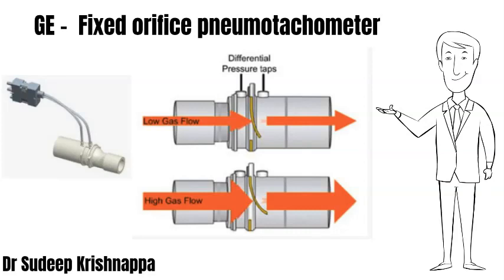In order to overcome this, the restrictor used is constructed in the form of a flap made of a synthetic material called Mylar. At low flow states, the flap is in its natural state, forming a small slit-like orifice, which generates a measurable differential pressure despite low flow levels. As gas flows increase, the flap opens more, reducing resistance to flow while still generating a pressure drop so that flow can be measured. There is a one-to-one correspondence between each flow rate and the pressure drop it creates.